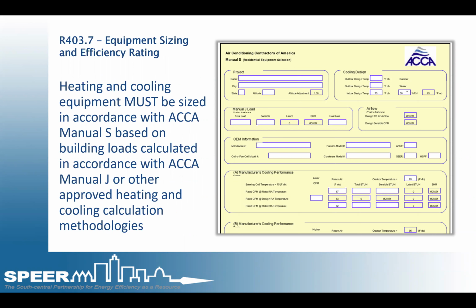R403.7 equipment sizing and efficiency. So in 2015 and 2018, using Manual S and Manual J is mandatory, but it is not mandatory to turn these in or have a third-party verifier review them. However, if the code official or third-party verifier requests these, it must be shown that they were used to design the system.